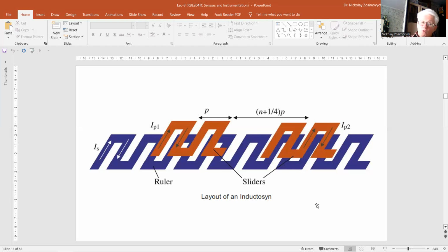The slider consists of two short coils with the same periodicity as that of the ruler. However, the geometric distance between the two parts of the slider is proportional to n plus 1/4 of a geometric period p. The Inductosyn is activated in a similar way as the resolver. The slider coils are supplied with AC currents, I1 and I2, with a half-pi phase difference. The ruler receives the sum of the two induced voltages according to the equation you can see previously. Again, the amplitude of the output signal is almost independent of the slider position, and the phase is a measure for the displacement.